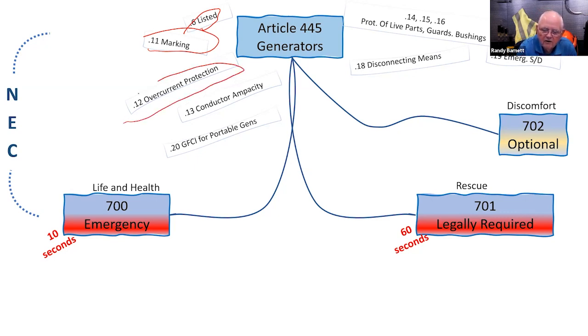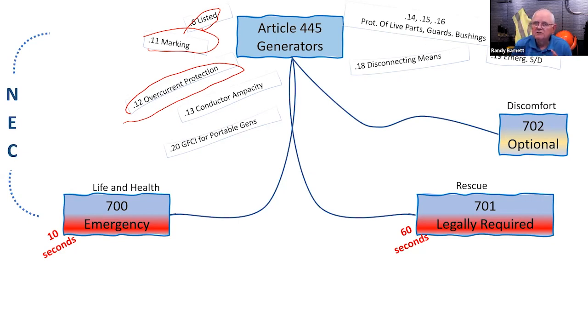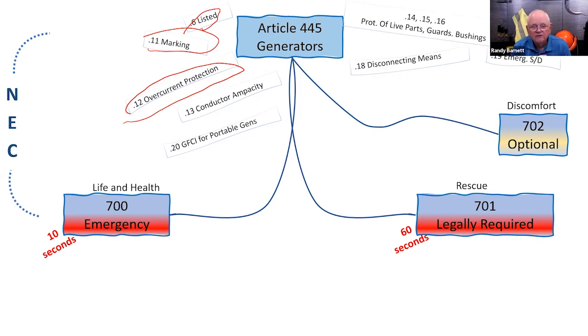Overcurrent protection is required — no surprise there. It actually gives some options and talks about inherent protection. That's not a fuse or a circuit breaker. If you're loading down an individual generator, you can hear it slow down. As you load it down, the voltage will start to drop off as well, and the unit will trip off the line and protect itself. We also talk about in Section 445.12 about other types of overcurrent protection, of course.